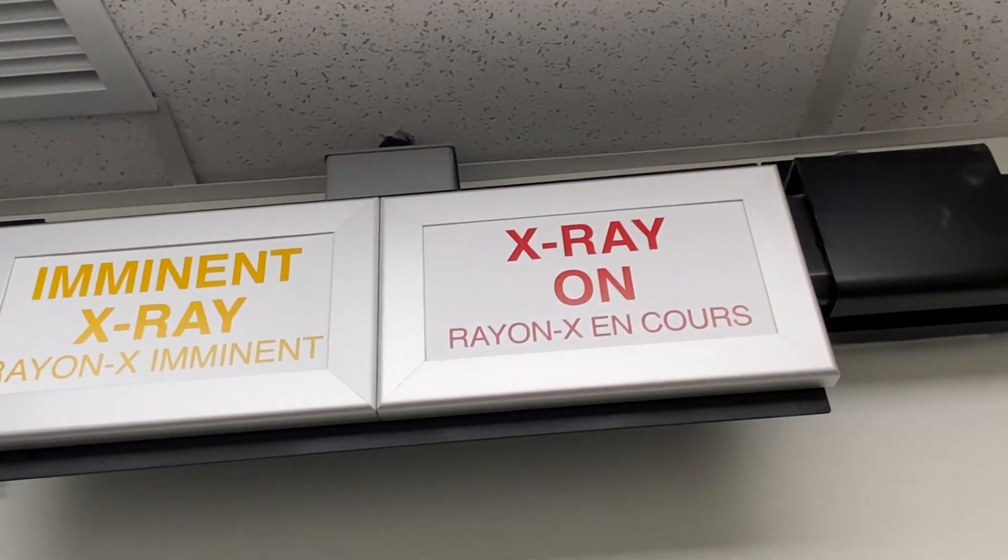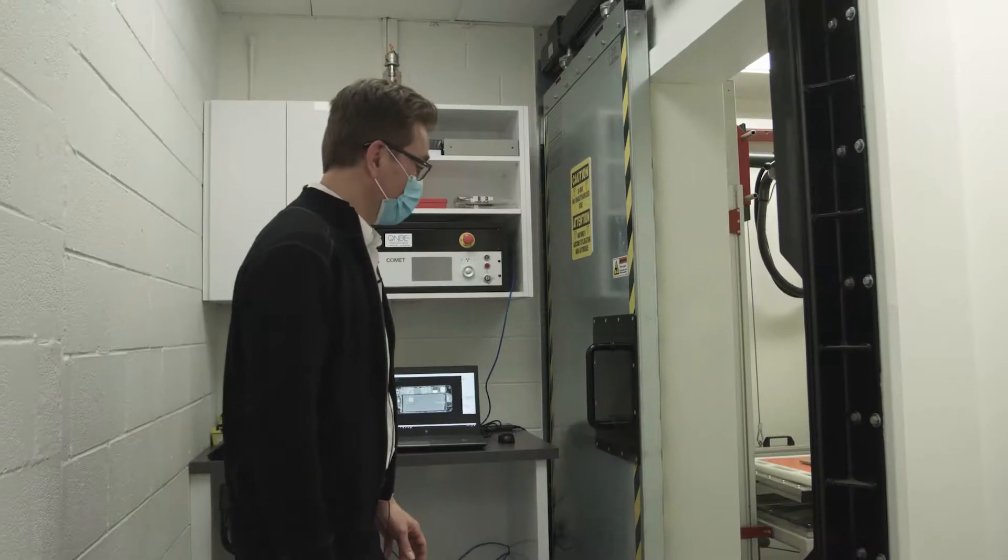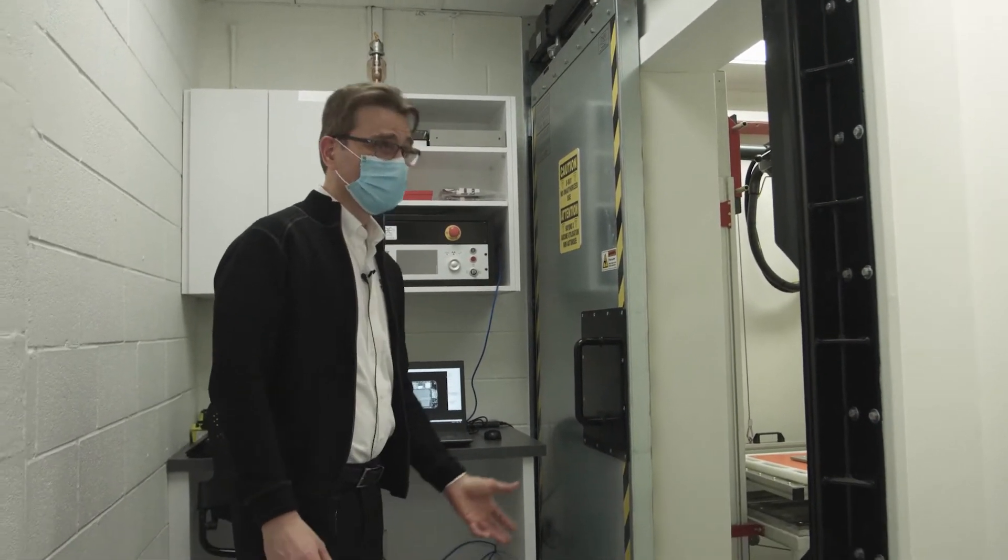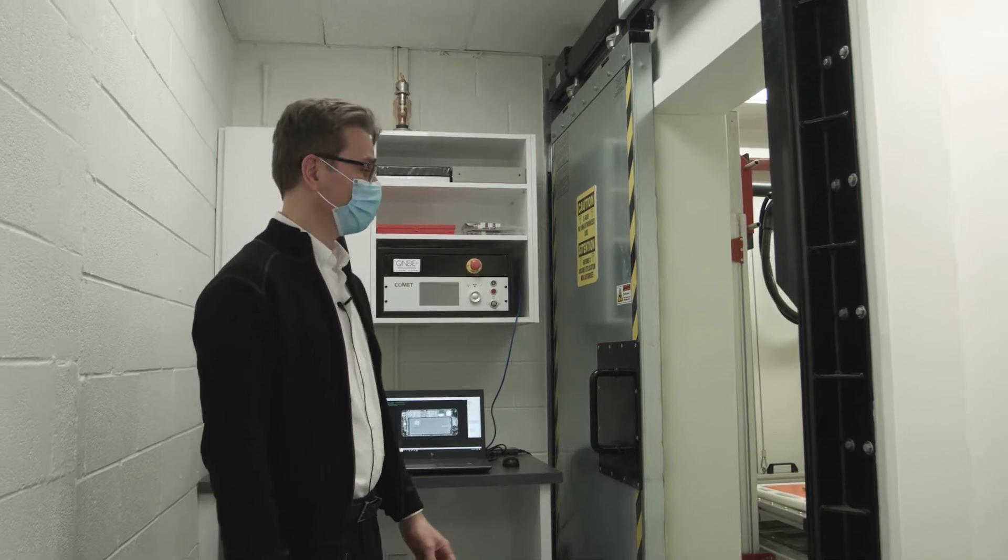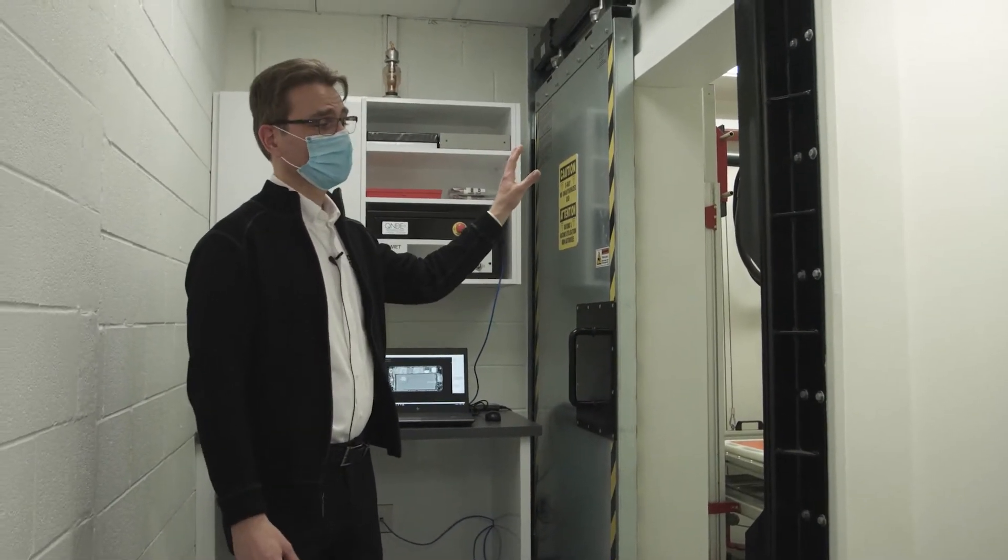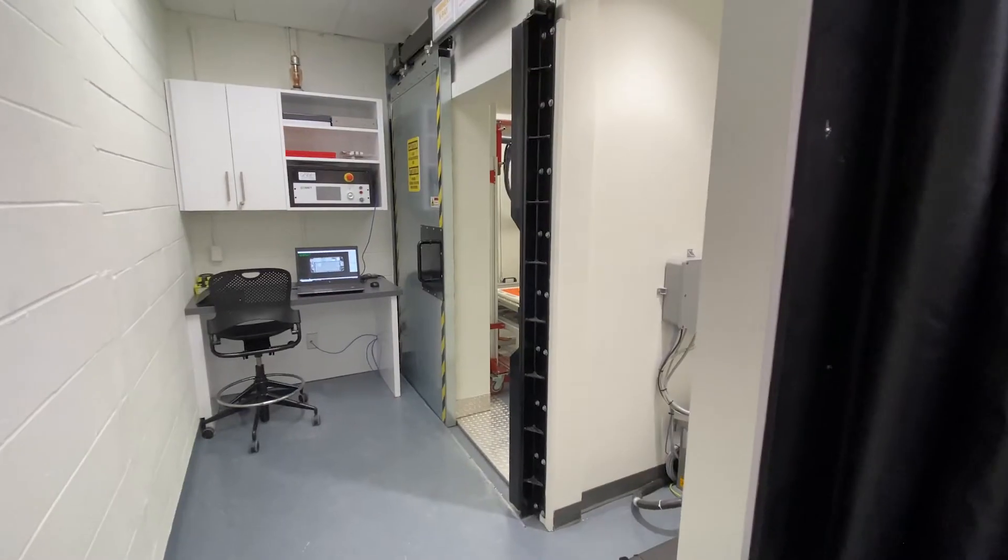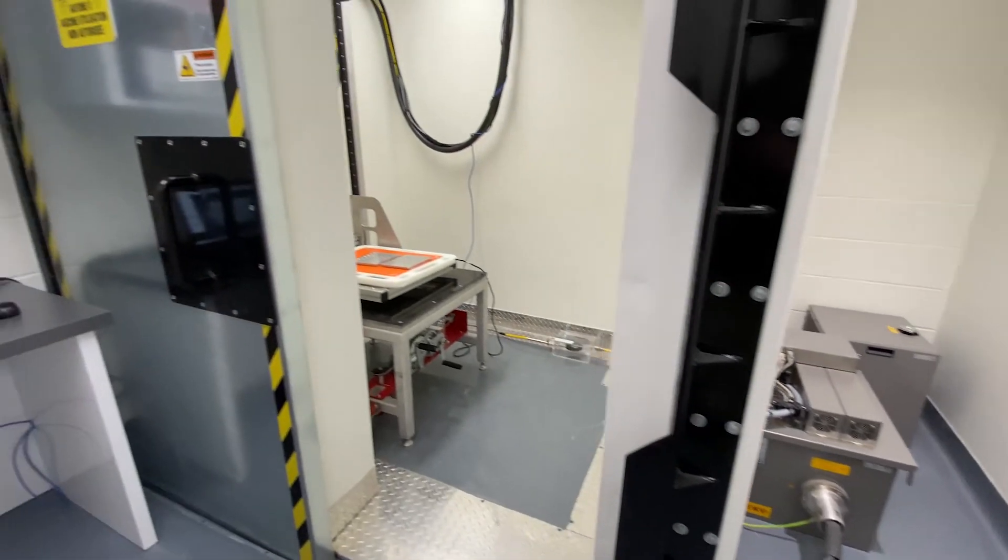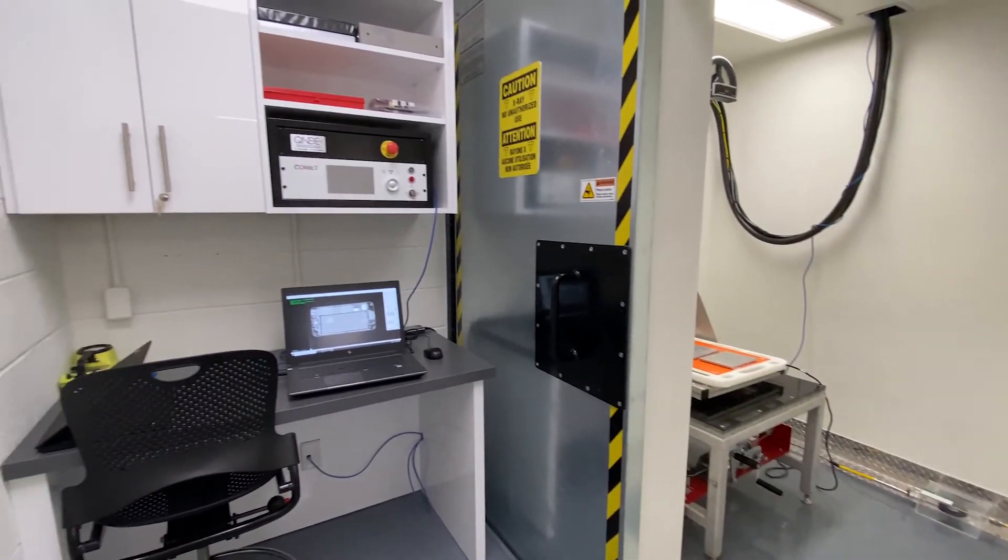And the vast majority of that is radiography. So we're looking at this is actually a Comet constant potential 220 kilovolt peak x-ray tube, with its generator and a cooling system. And so this enables us to run this pretty well as often as we want to.